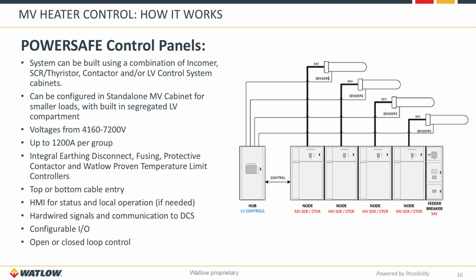If you have a small system with a single heater and you just need a single cabinet, we can combine the low voltage and medium voltage into a single cabinet without the necessity to have an incomer and or the separate low voltage control panel. That allows you a single cabinet with a single heater to control that particular heater as needed. For larger systems where you have to stack up multiple cabinets to get the total overall power or the number of circuits needed to control that particular heater, we do offer the multiple arrangement of cabinets here so you can stack those up as needed.